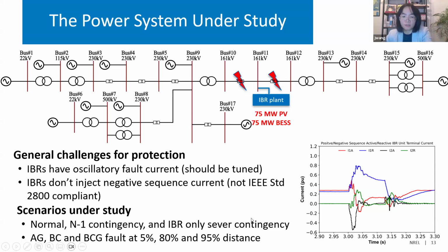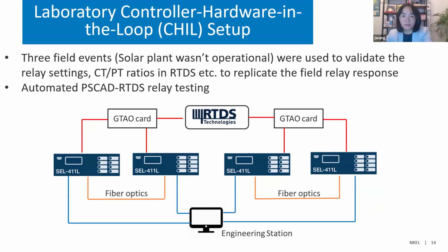For the study, we run through the normal N-1 conditions and the IBR only scenario. And we run the AG, BC, and BCG faults at different locations, 5%, 80%, and 95% distance. So this shows the system and the scenario we run. And we set up the laboratory controller hardware in the loop setup, see here. As you can see, we have the PSCAD run the full study. We got the contingency data and replay it in RTDS. And from RTDS, we have all the CT, PT signals come out through the GTAO card, and then connect with the SEL 411L relay. We got all the relay settings from our utility partner, and we use the 3 field events to validate the relay settings and CT-PT ratios to replicate the field event. And we did auto scripting to run through all the testing.